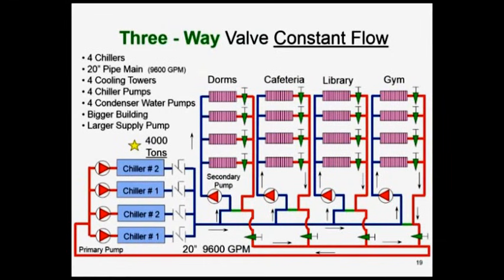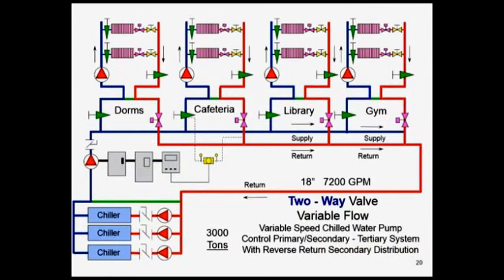Here's the old-fashioned way, 30 years ago: constant flow, 3-way valves, and you see the flow rate was 9,600 GPM in this chiller plant. So if you're trying to balance this campus, it's 9,600 GPM. You've got 2,400 GPM to each building at a 10-degree delta T, 2.4 GPM per ton, and you've got constant flow. So you're going to give the dorm, the cafeteria, each building, 2,400 GPM whether they need it or not. So you're wasting a lot of water, and you have to have those 4 chillers. Now, as soon as I go to 2-way valves, I drop back to 3 chillers.